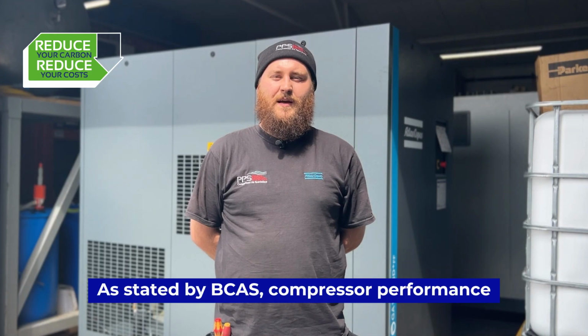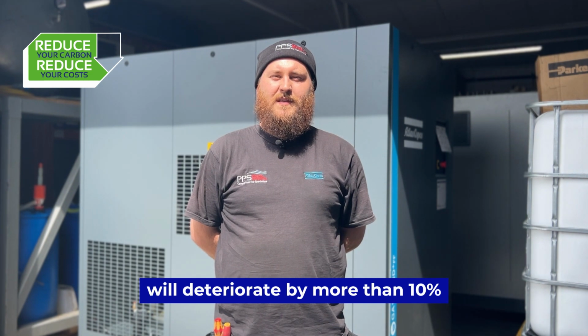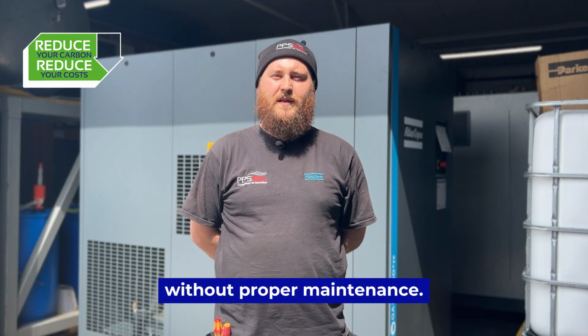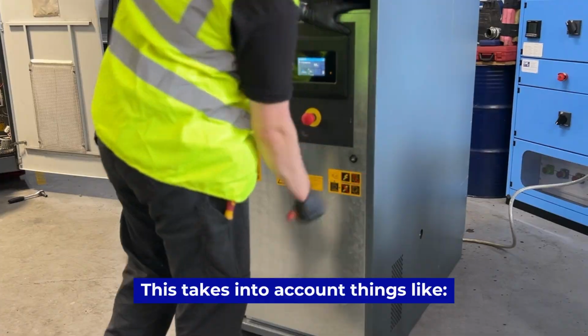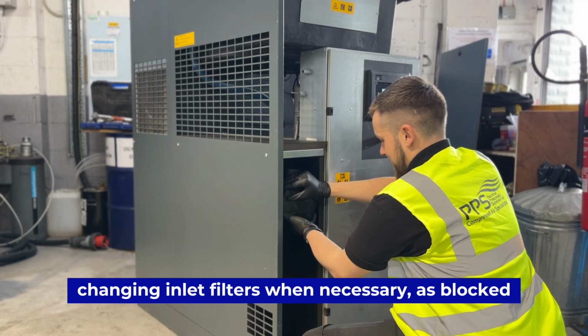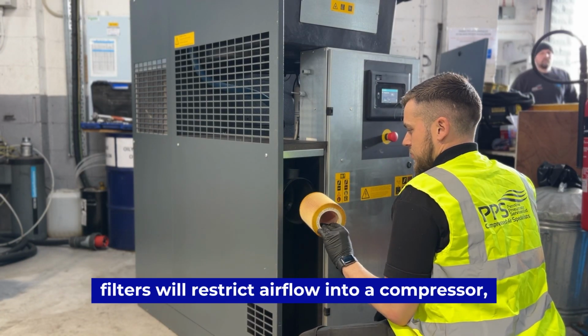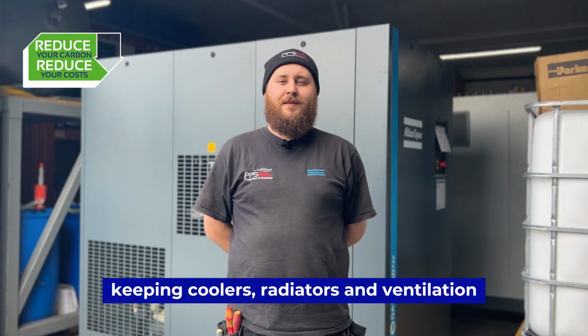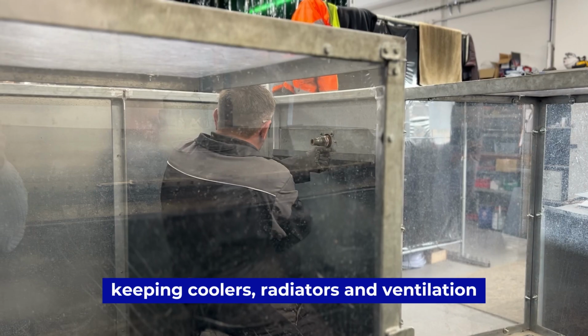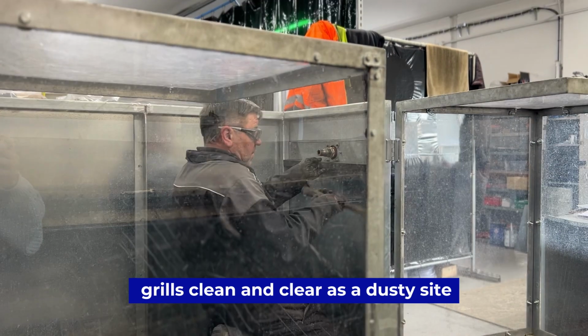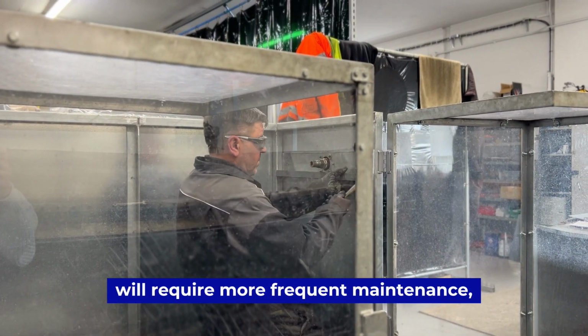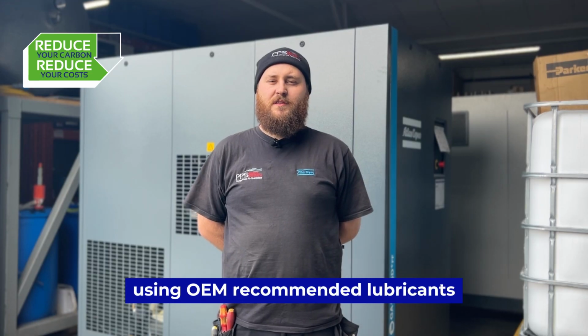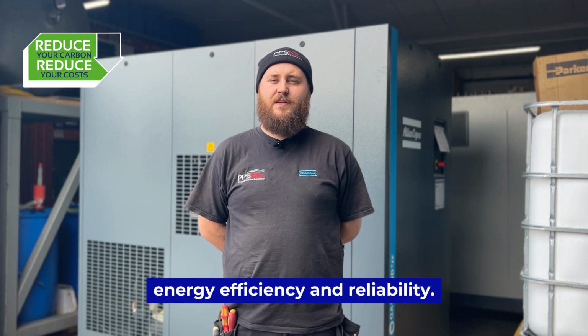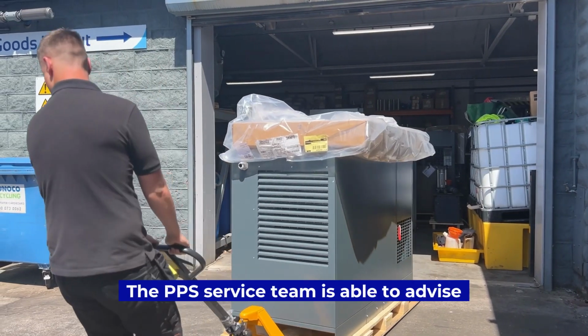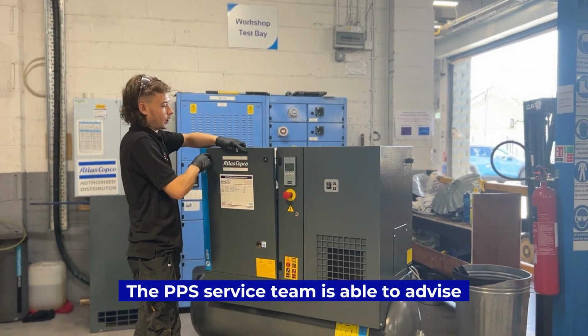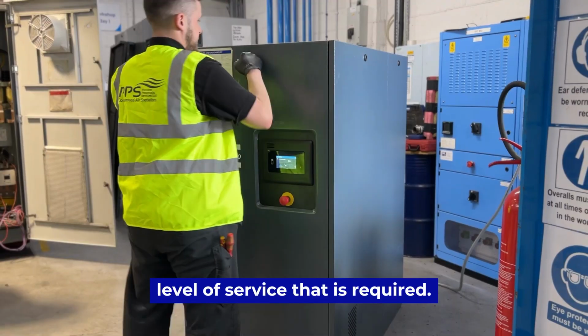As stated by BCAS, compressor performance will deteriorate by more than 10% without proper maintenance. This takes into account things like changing inlet filters when necessary, as blocked filters will restrict airflow into a compressor. Keeping coolers, radiators and ventilation grills clean and clear, as a dusty site will require more frequent maintenance. Using OEM recommended lubricants and genuine spare parts to ensure energy efficiency and reliability. The PPS service team is able to advise and guide you on the correct level of service that is required.